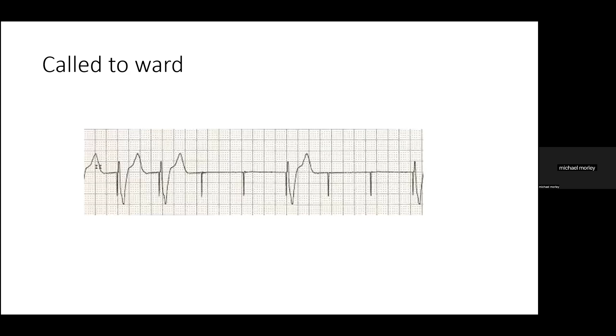But then we have some pacing spikes which are not followed by QRS complexes. So these pacing spikes have not been sufficient to depolarize the heart to initiate the action potential at the pacing wire tip and lead to a ventricular beat. So we need to have a look and have an understanding of pacing and the temporary pacemaker box. And if you understand how a temporary pacemaker system works, then really you've got pretty good grounding in how all pacemakers work.